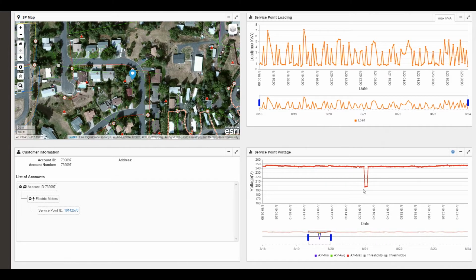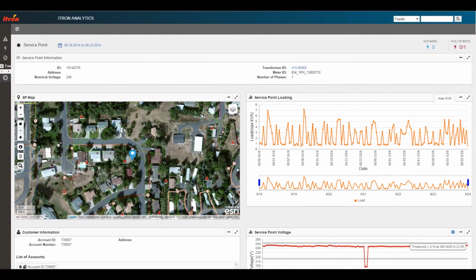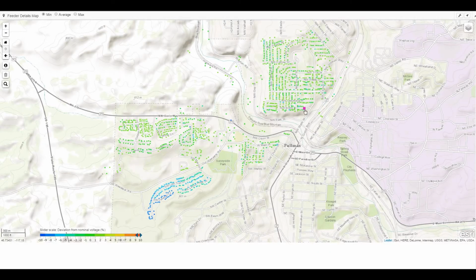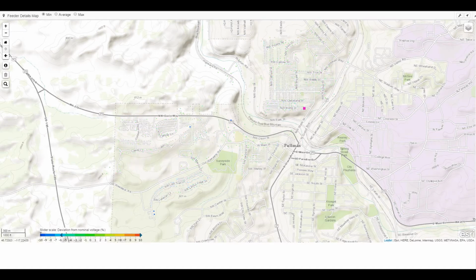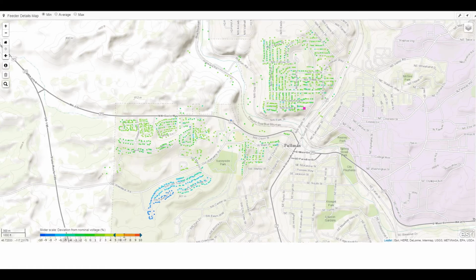For a more comprehensive view of voltage trends, the planner reviews voltage levels throughout the entire circuit. Symbols indicate voltage at each service point, while locations that exceeded high or low voltage thresholds are indicated with markers. A slide control enables the planner to dynamically visualize voltage levels across the circuit. The planner is able to select any service point or transformer and review detailed information.